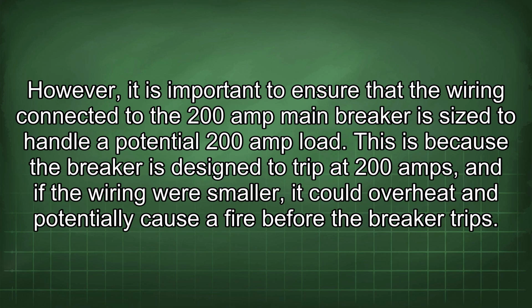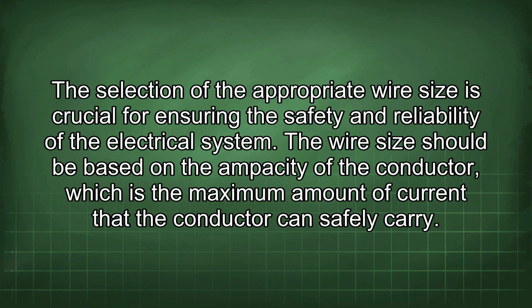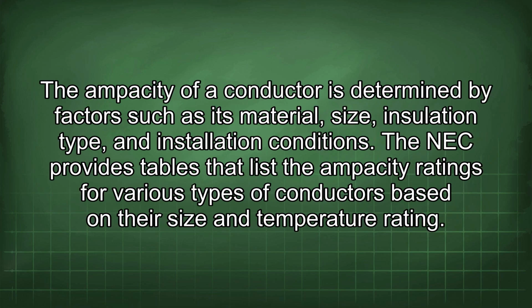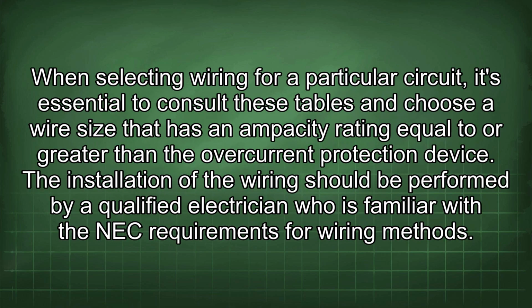This is because the breaker is designed to trip at 200 amps, and if the wiring was smaller, it could overheat and potentially cause a fire before the breaker trips. The selection of the appropriate wire size is crucial for ensuring the safety and reliability of the electrical system. The wire size should be based on the ampacity of the conductor, which is the maximum amount of current that the conductor can safely carry. The ampacity of a conductor is determined by factors such as its material, size, insulation type, and installation conditions. The NEC provides tables that list the ampacity ratings for various types of conductors based on their size and temperature rating. When selecting wiring for a particular circuit, it's essential to consult these tables and choose a wire size that has an ampacity rating equal to or greater than the overcurrent protection device.